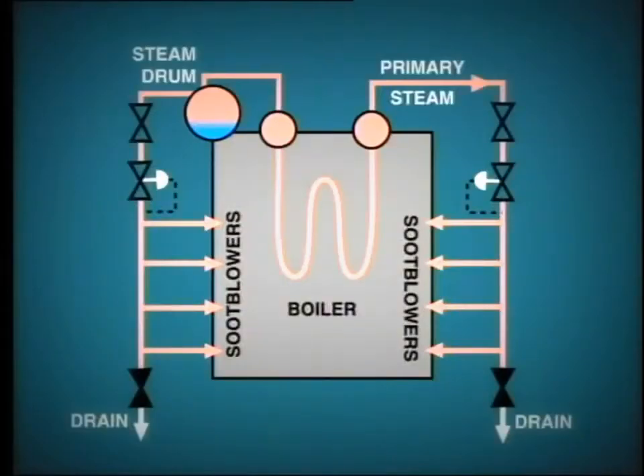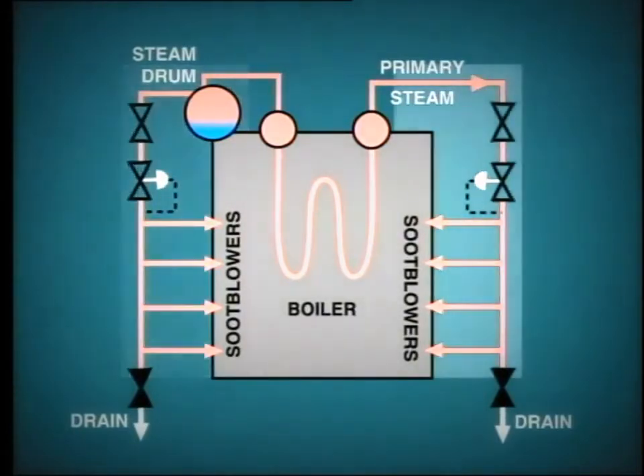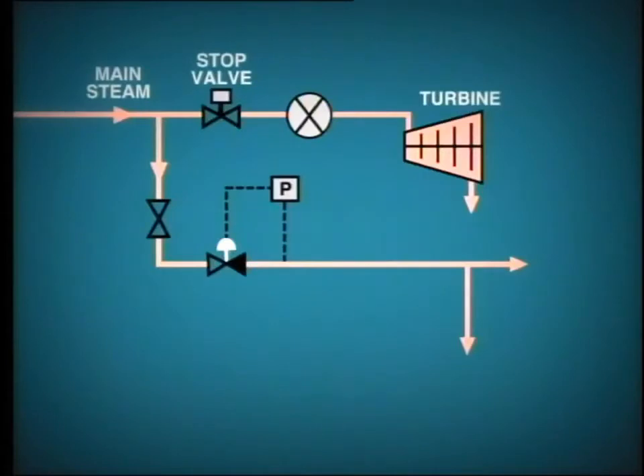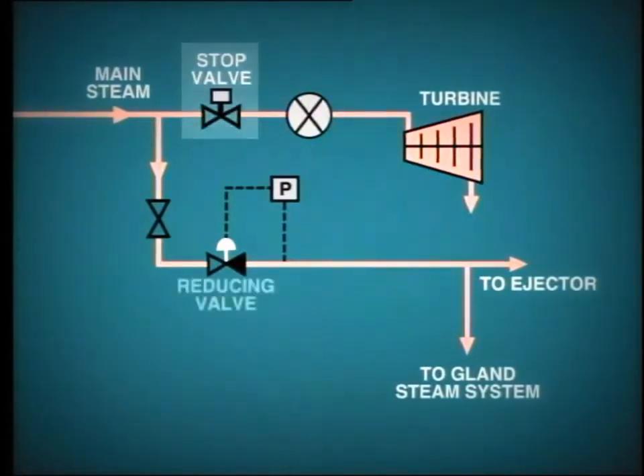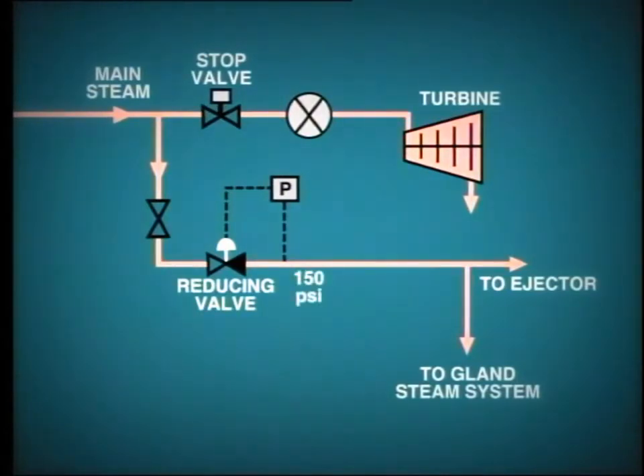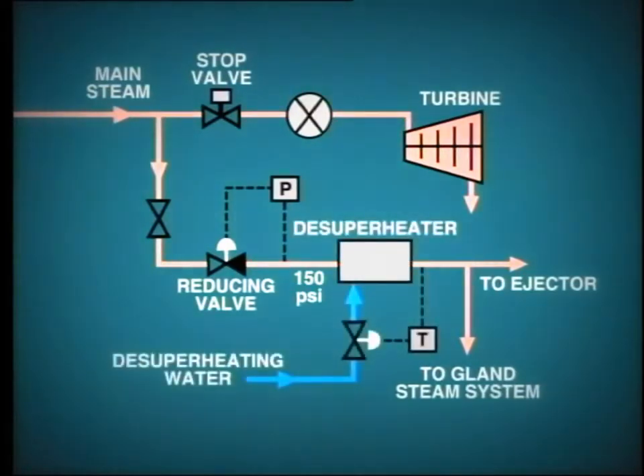Soot-blowing steam for the boiler is usually taken directly from the boiler itself, either from the drum or the first stage of superheat. For the turbine steam auxiliaries, such as the air removal steam ejector and gland sealing steam, a direct supply is usually taken from the main steam line before the stop valve. This high-pressure steam then passes through a reducing station to bring the pressure down to, say, 150 psi.